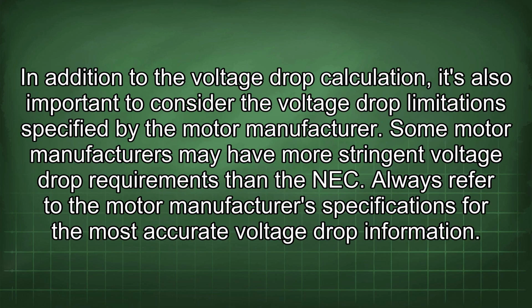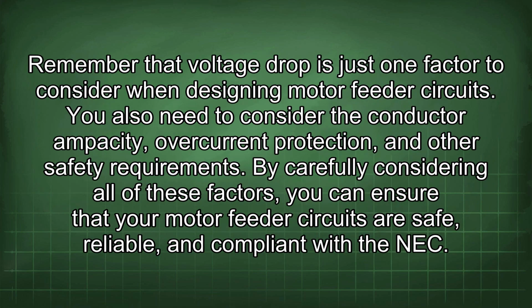In addition to the voltage drop calculation, it's also important to consider the voltage drop limitations specified by the motor manufacturer. Some motor manufacturers may have more stringent voltage drop requirements than the NEC. Always refer to the motor manufacturer's specifications for the most accurate voltage drop information. Remember that voltage drop is just one factor to consider when designing motor feeder circuits. You also need to consider the conductor ampacity, overcurrent protection, and other safety requirements. By carefully considering all of these factors, you can ensure that your motor feeder circuits are safe, reliable, and compliant with the NEC.